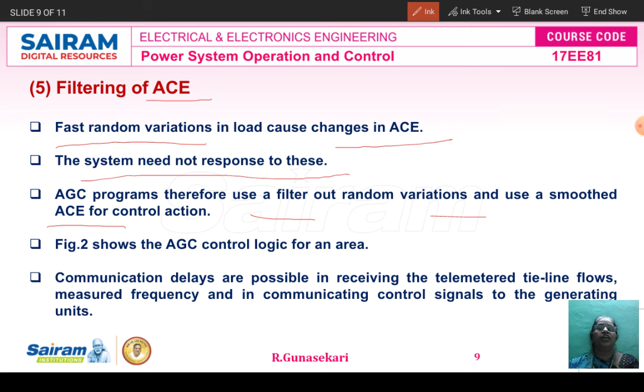The figure shows the area control logic, the generation control logic diagram. In this diagram you can see the frequency F as plus, and F naught, the base frequency, as minus. B is the frequency bias block, giving B into del F variations, which is added. Here you see the telemetered tie line flows, and the scheduled tie line power, del P tie. That gives the area control error. The area control error equals del P tie plus B into del F. This is the formula for area control error.